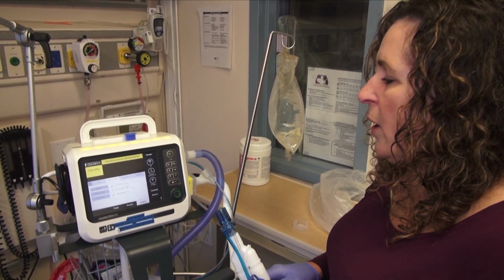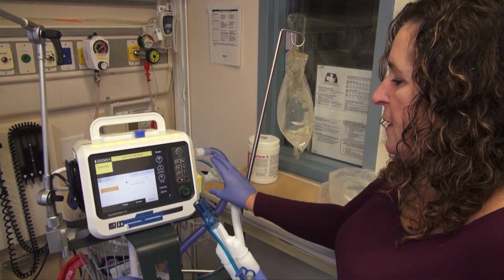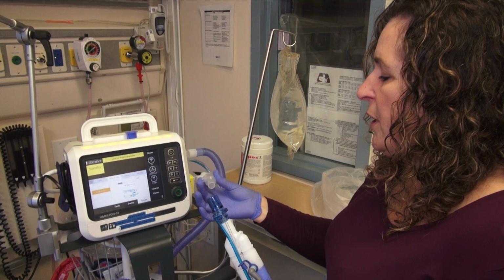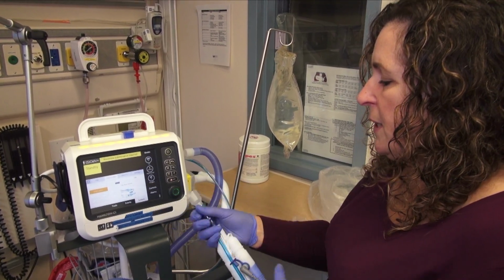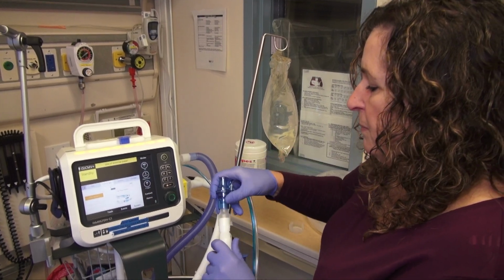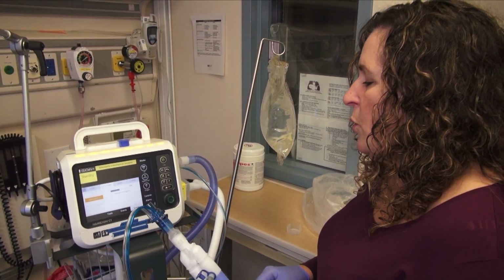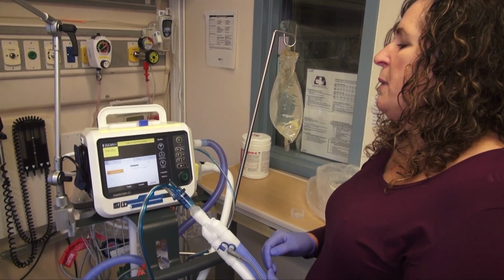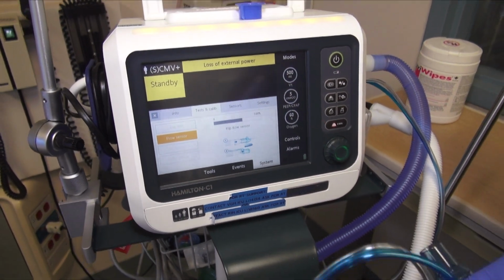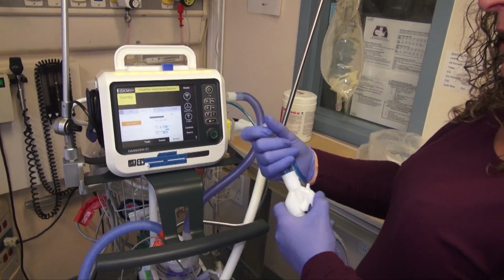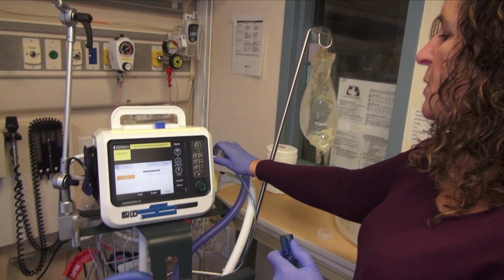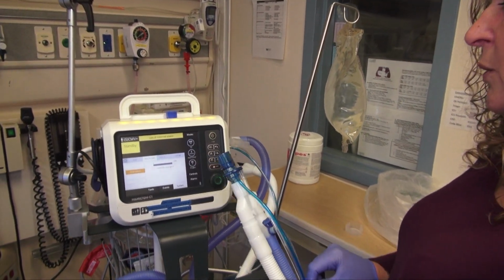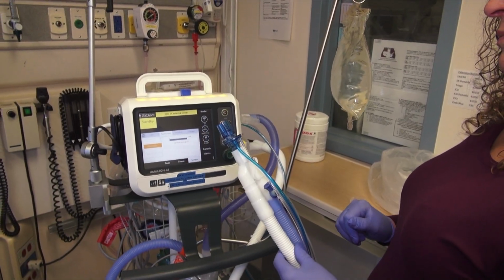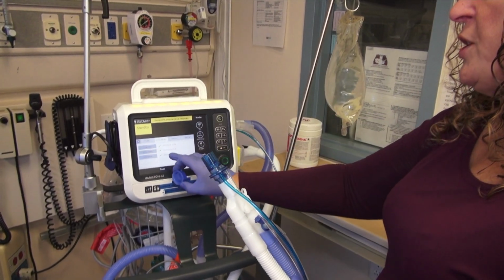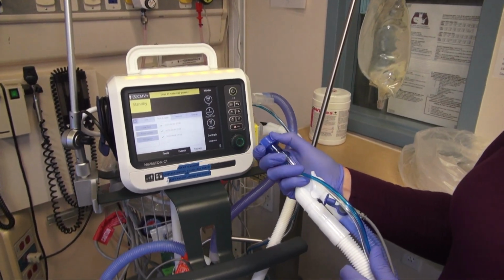leak test. Going on to the flow sensor test, we hit that. It says to disconnect the patient, which we have. We're going to use the little device here, place it in the flow sensor and flip it. Calibration will be in progress. And your next message, when that's done, will come up on the screen. Okay, so here's the screen. You're going to flip it again and take the device out and hook it here. Then it will continue on with the calibration. All right, and you've got a green check mark, so the flow sensor is checked and ready for use.